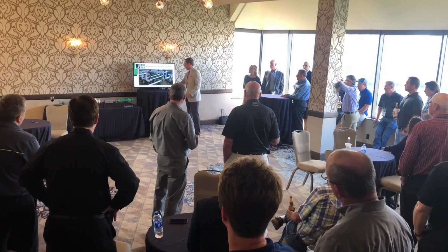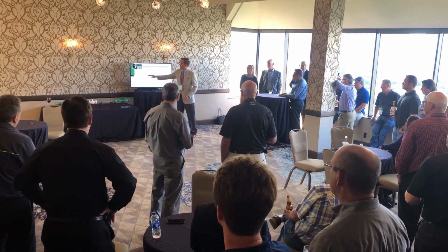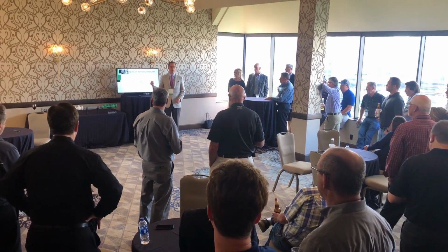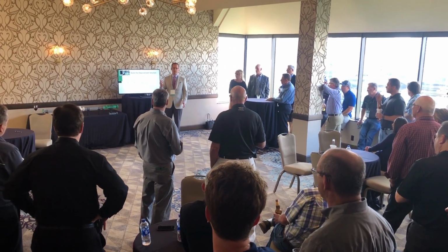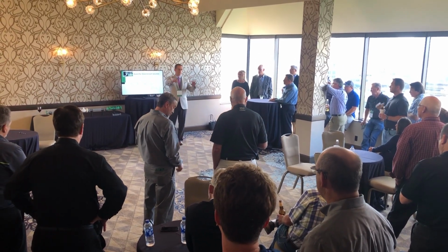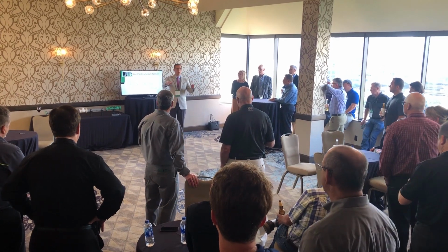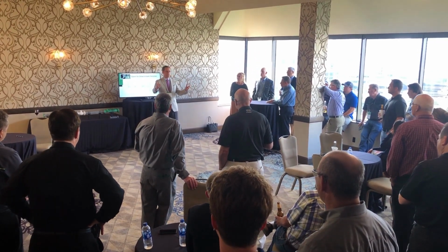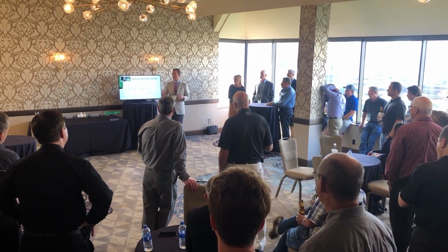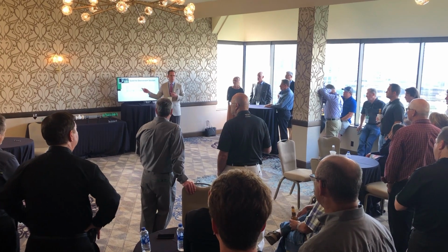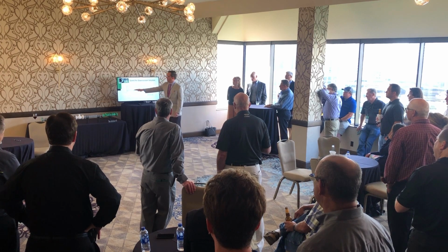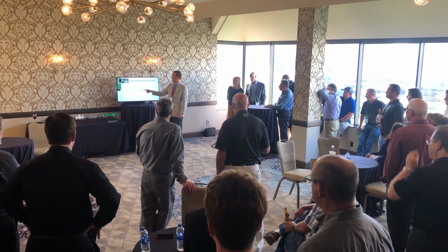So we learned that the upstream side of the tube really didn't need this sweeping end treatment in order to get a repeatable profile at the meter. And this got our cranks turning, because I've got a couple other fabricator companies here, which I really appreciate you all coming. So we all experience this. We build these systems for a lot of our different clients, and so we get to see all these different varieties of end treatments. Well, because of what we discovered on M3, it got our cranks turning, thinking, you know what? We now have an upstream end treatment that never leaves the center line of the meter.